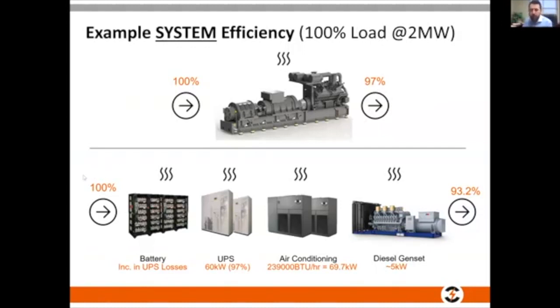Comparing back to a static UPS by example, we have losses from our battery. Our static UPS is 97, I might actually be a little low, maybe 98% efficient. But you also have losses from the air conditioning, losses from the diesel generator preheaters, pre-lubricators. It's not on, but it's not completely cold, it has to be preheated. There is energy that's required. When you take in all these losses, you get to about 93% system.